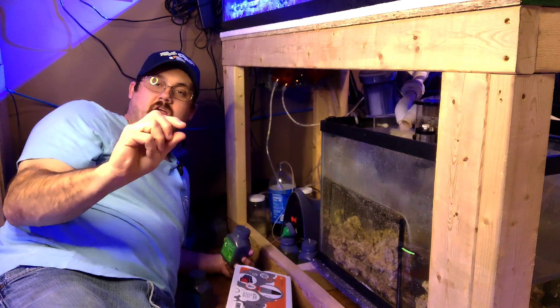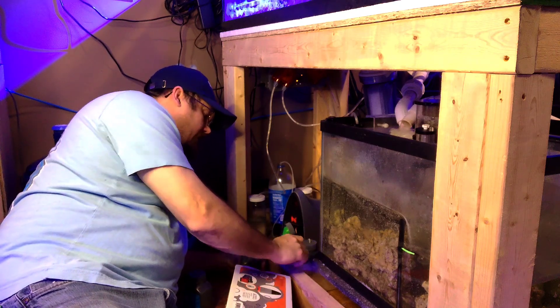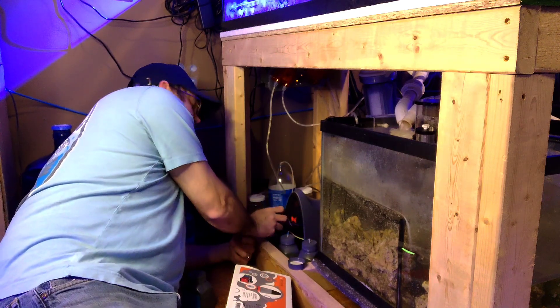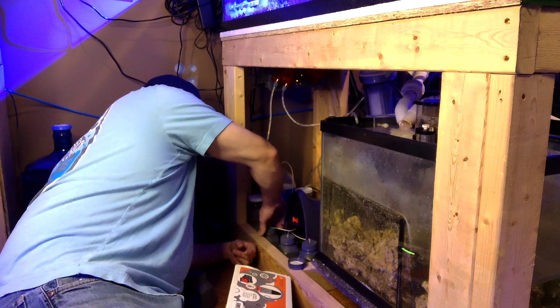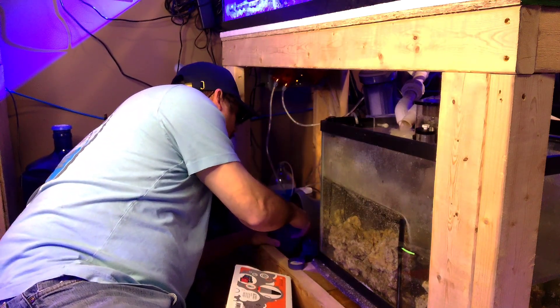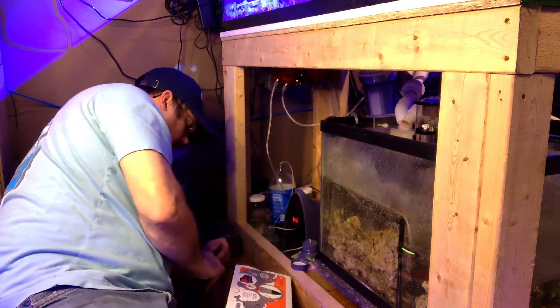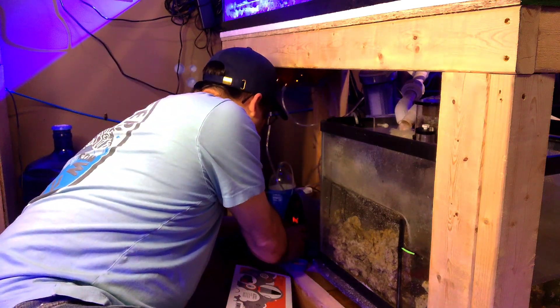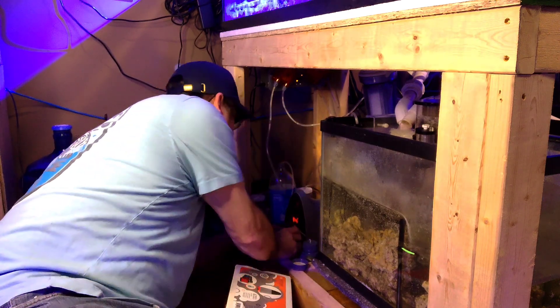Sometimes when you change this you'll notice there's quite a bit left. That's because, just to err on the side of caution, it will think that the bottle is empty when it's not. So it'll say the bottle is empty and it really isn't. In that case, all you have to do is just reset the level for your reagent and then change it when it's really empty — like mine are right now. So I've got to make sure I get these changed before it draws air inside the lines.